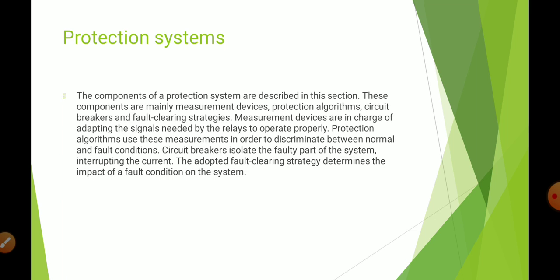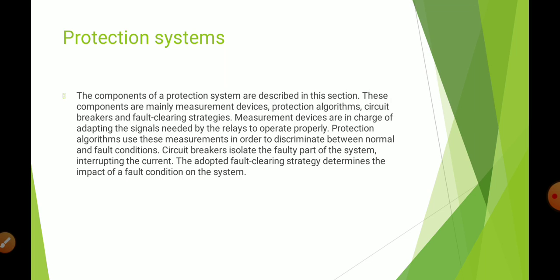Protection systems. The components of a protection system are described. These components are mainly the measurement devices, protection algorithms, circuit breakers, and fault clearing strategies. Measurement devices are in charge of adapting the signals needed by the relays to operate properly. Protection algorithms use these measurements in order to discriminate between normal and fault conditions. Circuit breakers isolate the faulty part of the system, thus interrupting the current. The adopted fault clearing strategy determines the impact of a fault condition on the system.